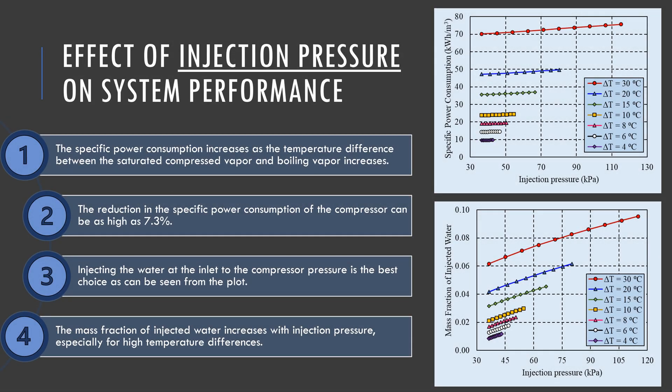From the simulation results, the water injection pressure and temperature lift across the compressor affect both the specific power consumption of the compressor and the mass fraction of injected water — both defined relative to the desalinated water amount. As the injection pressure and temperature lift increase, both the mass fraction of injected water and the specific power consumption increase. The reduction in specific power consumption can be as high as 7.3%, which is significant. Injecting water at the inlet pressure of the compressor is the best choice, and the mass fraction of injected water did not exceed 10% of the compressor inlet.